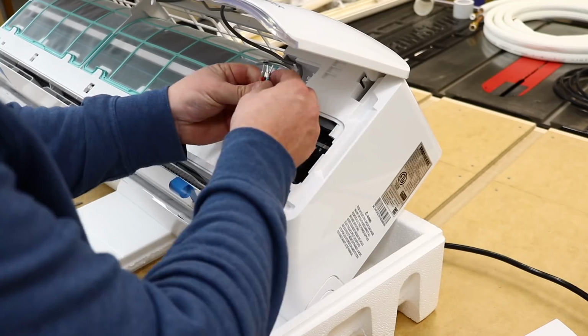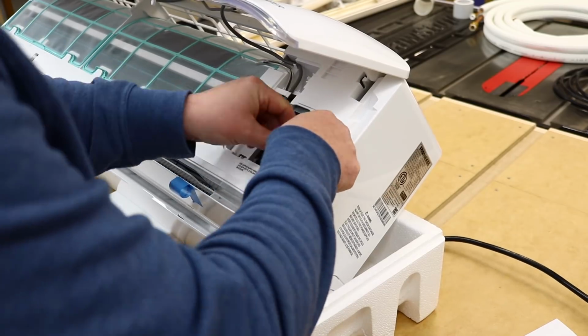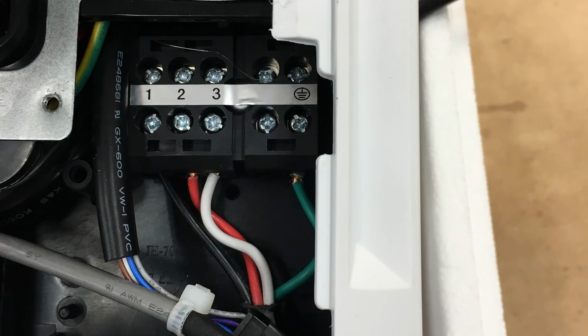I didn't have a way to get a shot of wiring this up, so here's a picture that shows how the wires are connected. The wiring terminals are not labeled anything other than 1, 2, 3, and ground. Based on the few units I've looked at, this is pretty common. It's imperative that you remember which color is connected to which number, because the terminal in the outdoor unit is exactly the same, and if you switch anything around, at best your unit won't function, and at worst you'll ruin your unit. The signal cable contained black, red, white, and green wires, and since green is commonly used for ground, I connected that to the grounding terminal. For the other three, I just went black 1, red 2, white 3.